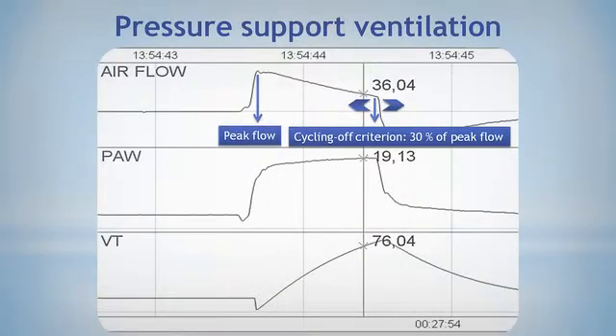It's a pressure-limited and flow-cycled mode, in which after the sensitivity setting has been triggered, the pressure increases until a pressure value is reached. This pressure value is maintained throughout the inspiratory cycle. The expiratory phase begins when the flow reaches a determined value, usually a percentage of peak flow value.